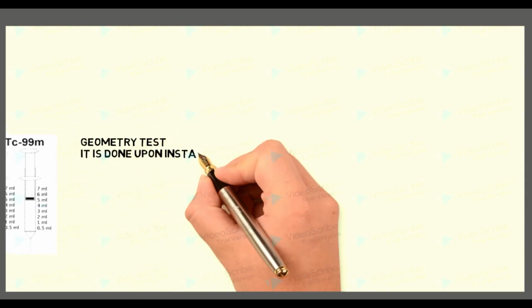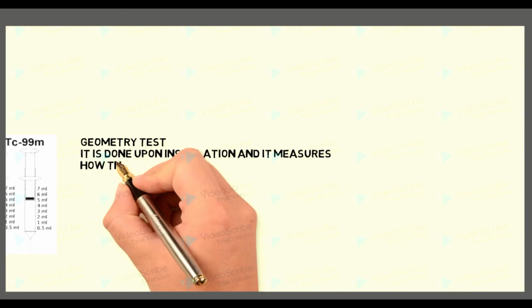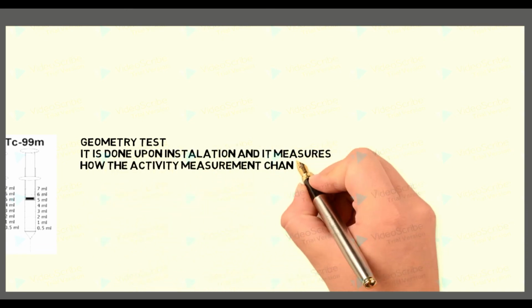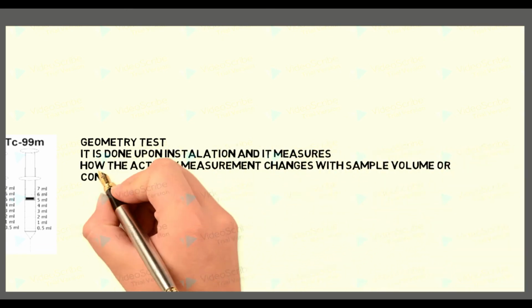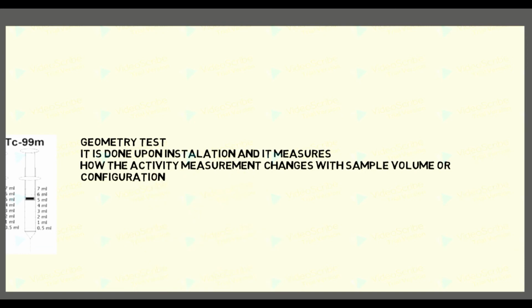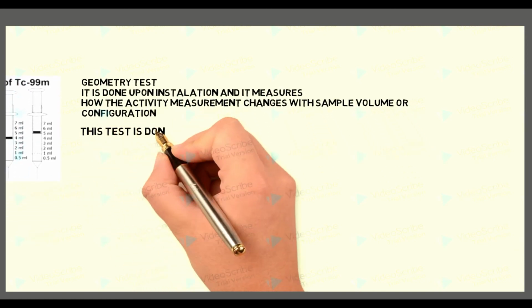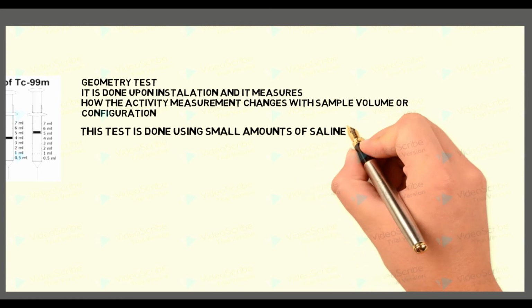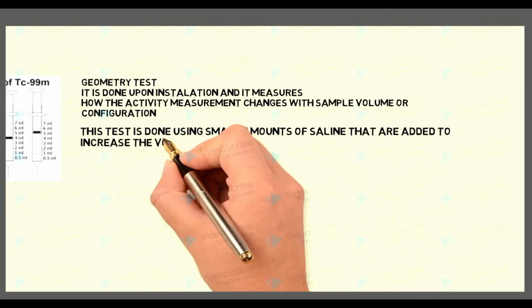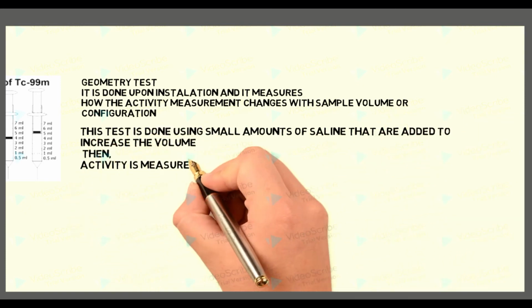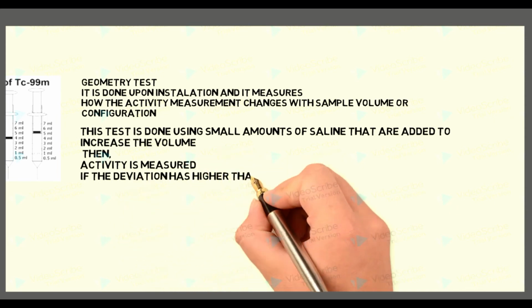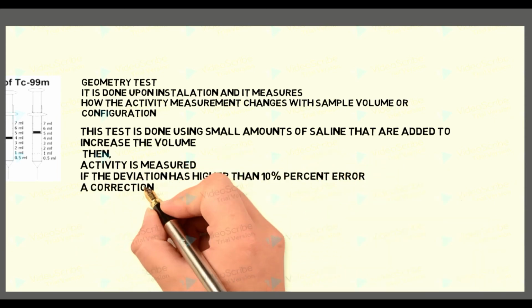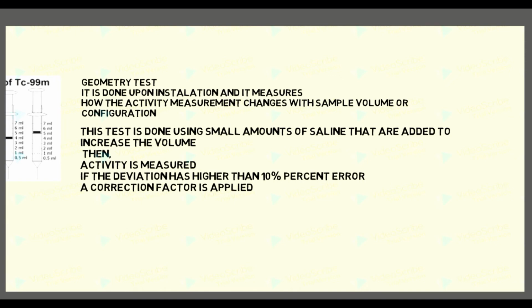A geometry test. It is done upon installation, and it measures how the activity measurement changes with the sample volume or reconfiguration. This test is done using small amounts of saline that are then added to increase the volume. Then, activity is measured, and if the deviation has higher than 10% error, a correction factor is also applied.